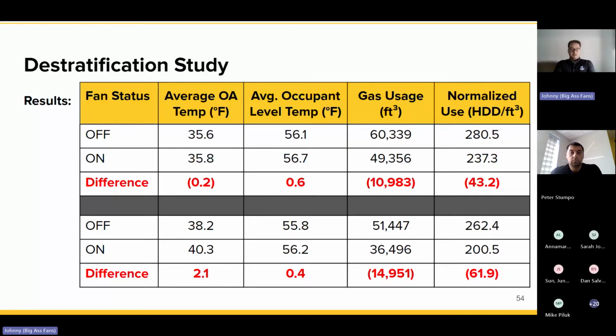With the fan on in the first test, we saw almost 11,000 cubic feet of gas reduced for just 1 week. On the second test, it was actually a little bit more pronounced, just based on some of the temperature conditions. This is typical, and we did not have an aggressive set point here. It's a hangar. The CLO level would be high. People are comfortable at a lower temperature, and still we saw a significant gas reduction. So we can extrapolate this. We do lots of warehouse projects where you're seeing 30% reductions in your gas usage.